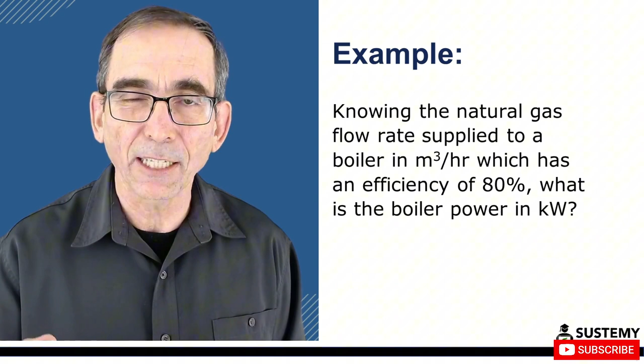For example, let's look at a situation where we know the natural gas flow rate supplied to a boiler in meters cubed per hour. Let's assume the boiler has an efficiency of 80% and we want to know the boiler output power in kilowatts. By making all the units explicit, it's hard to come up with the wrong answer. Here we have the gas flow rate of 10 meters cubed per hour at standard temperature and pressure. We have a gas calorific value of, say, 38 megajoules per meter cubed.